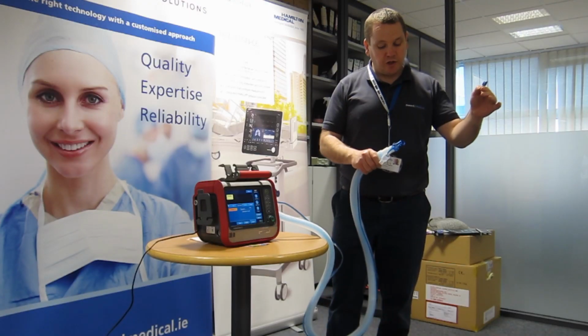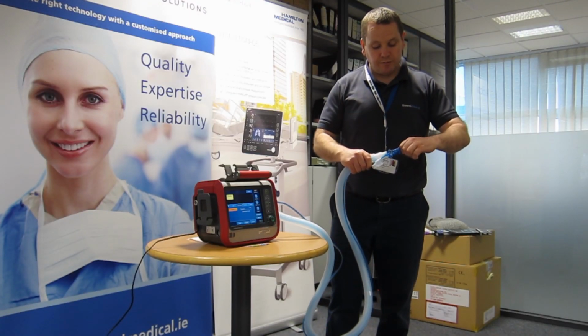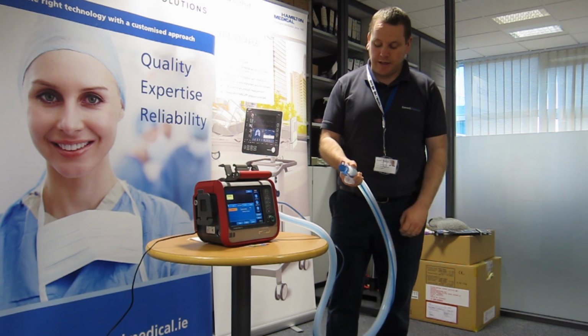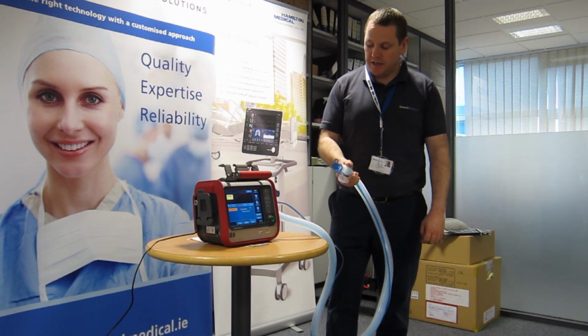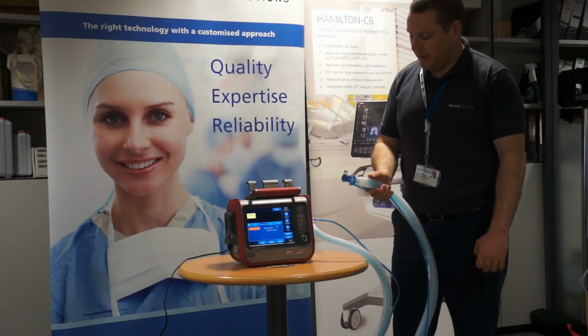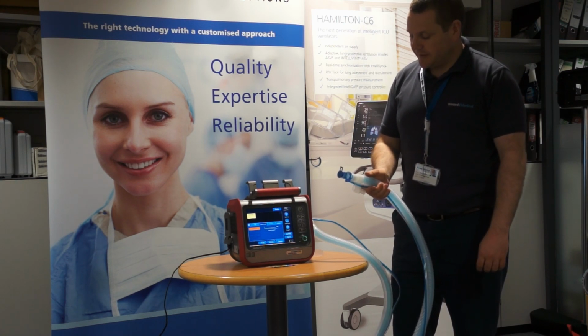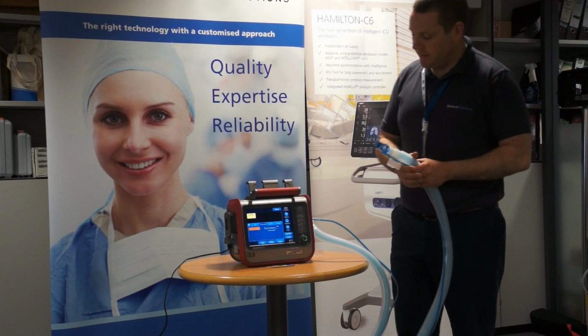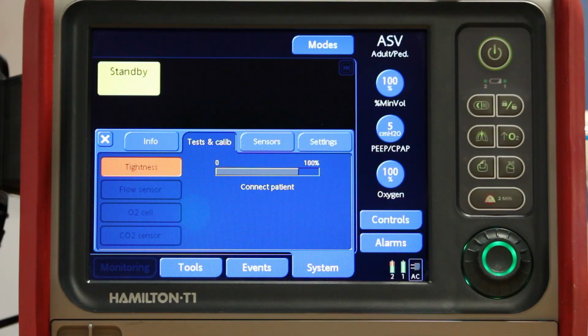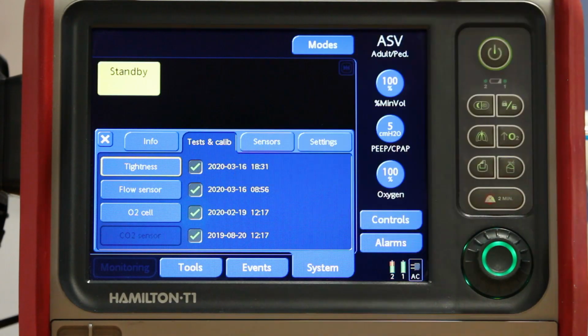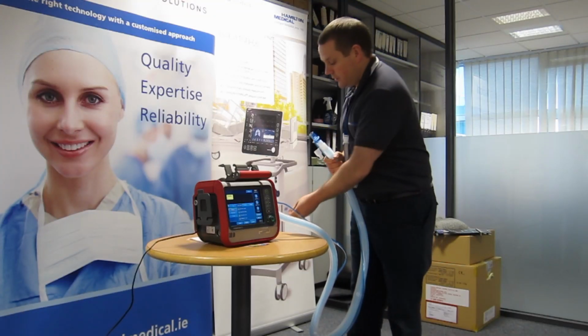So I either occlude the circuit with a gloved hand, or I can put the dust cover back into the circuit, and you hear the ventilator looking for a leak anywhere along. And that's it. So that's our tightness test complete. And then we get a green tick here, and the date and the time. The next one I'm going to do is the flow sensor.